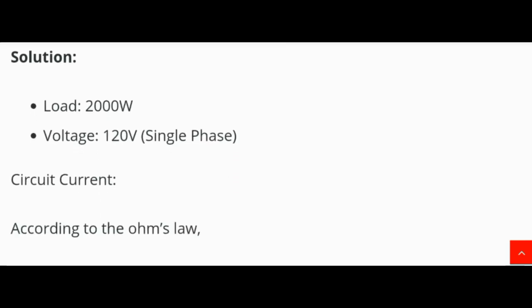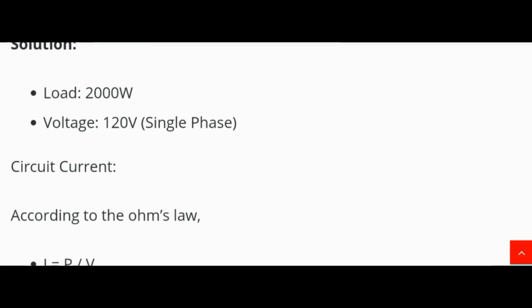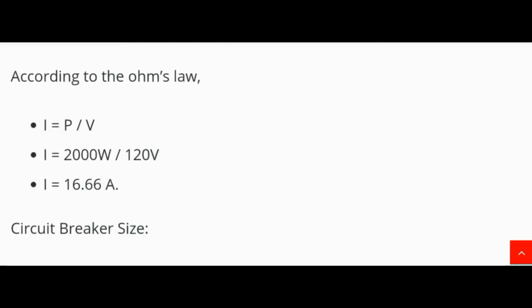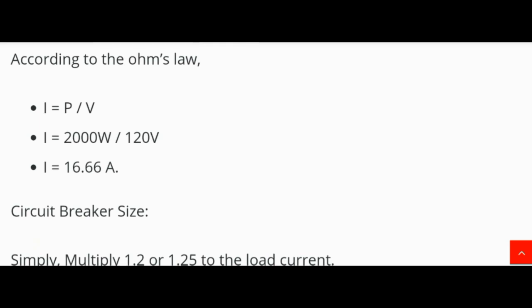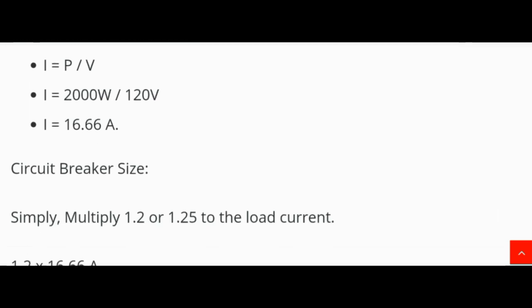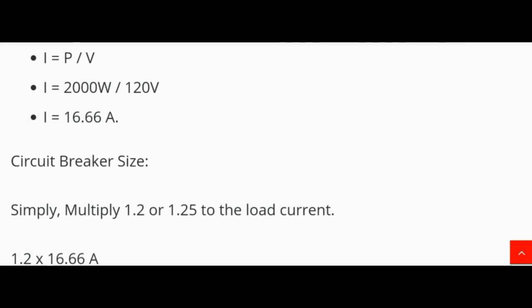Example 2: What is the appropriate size of circuit breaker for a 2000 watt, single phase, 120 volt supply? Solution: Load = 2000 W, Voltage = 120 V (single phase). Using Ohm's law: I = P / V = 2000 W / 120 V = 16.66 ampere.